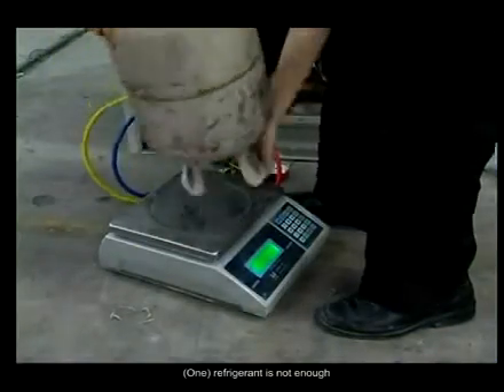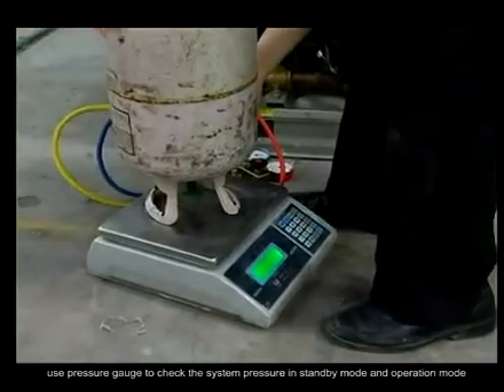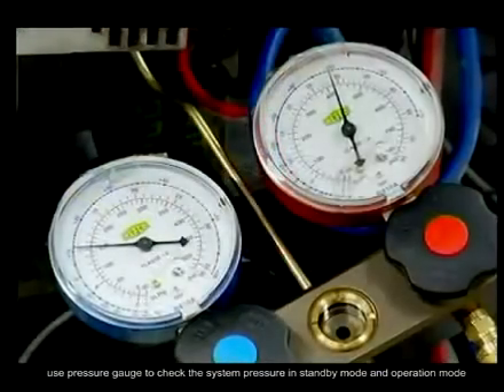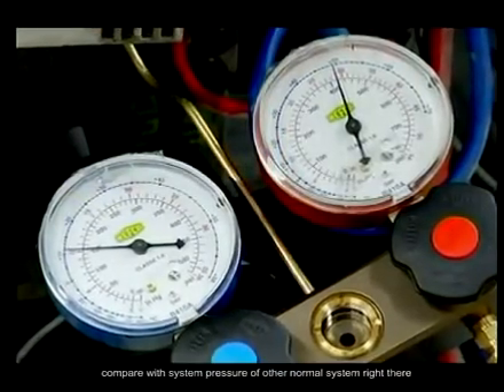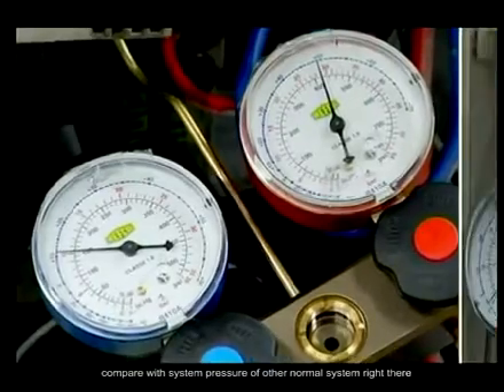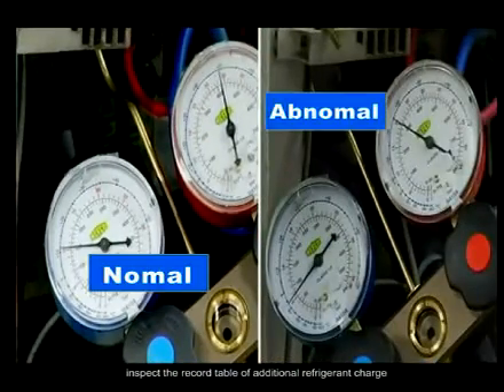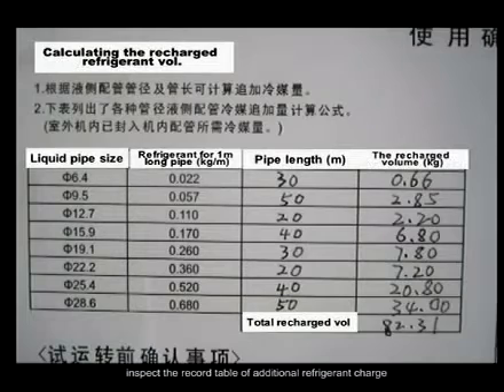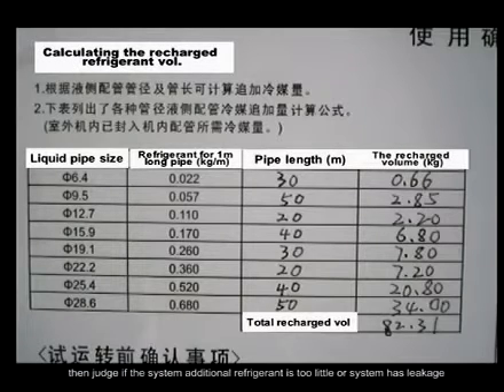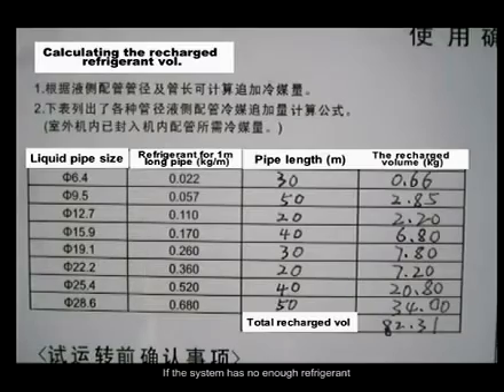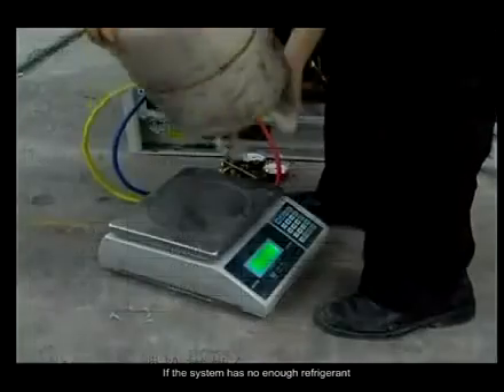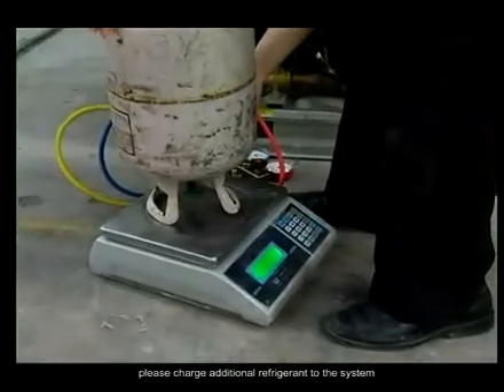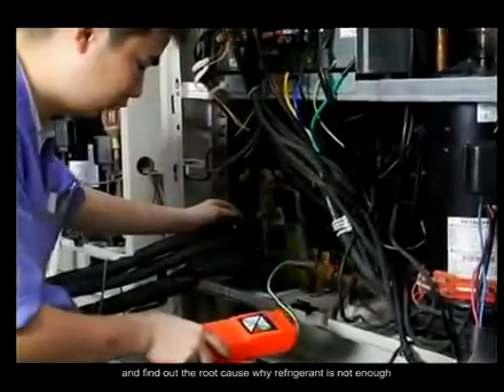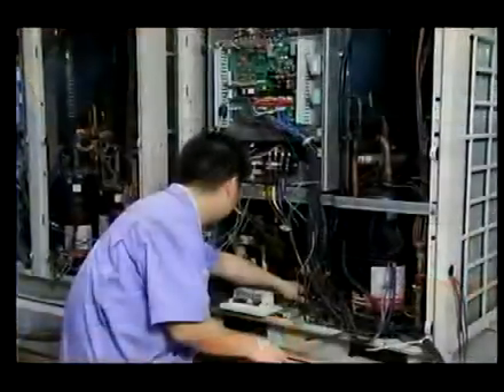1. Refrigerant is not enough. Use a pressure gauge to check the system pressure in standby mode and operation mode. Compare with the system pressure of other normal systems right there. Inspect the record table of additional refrigerant charge. Then judge if the system's additional refrigerant is too little or the system has leakage. If the system has not enough refrigerant, please charge additional refrigerant to the system and find out the root cause why the refrigerant is not enough.